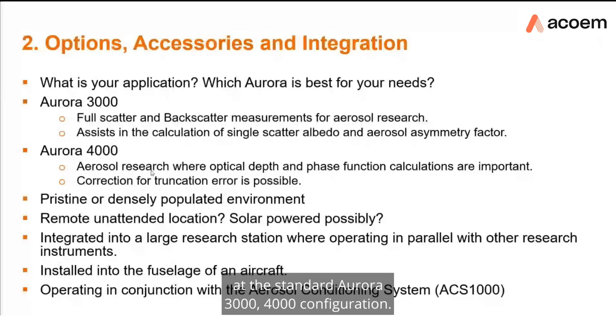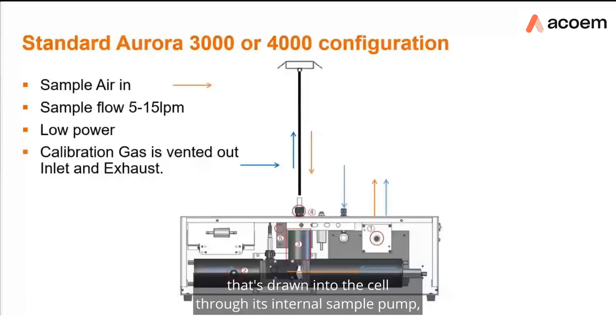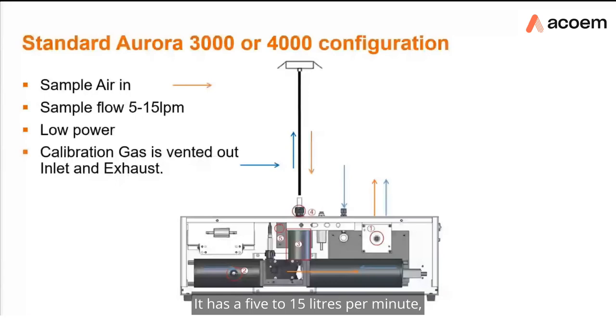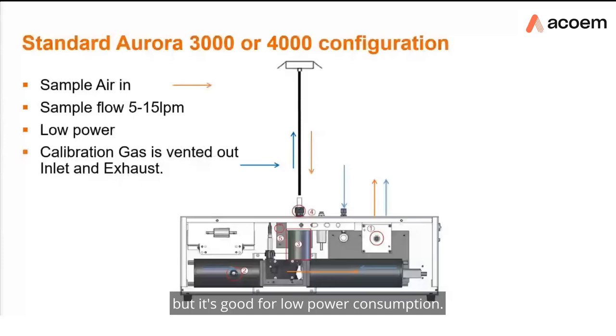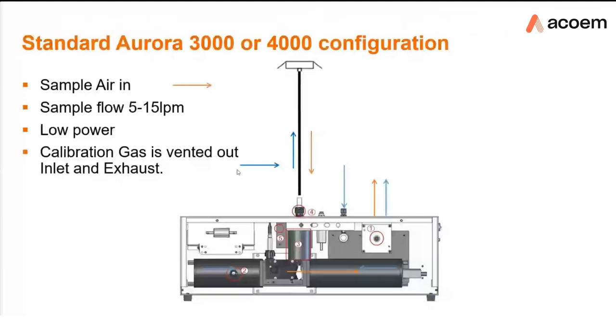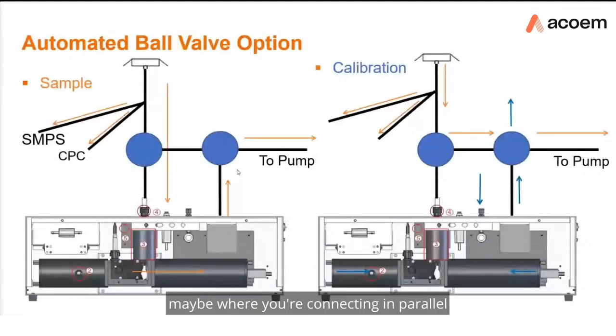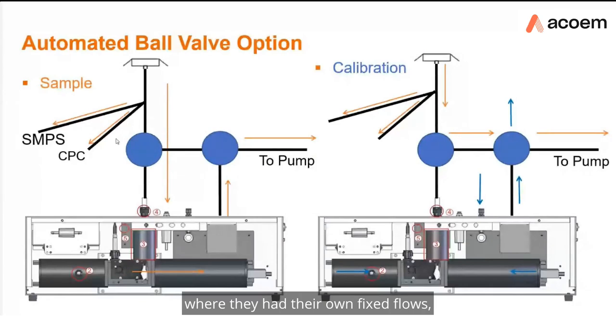The standard Aurora 3000 and 4000 configuration is a standalone setup where the sample inlet is drawn into the cell through an internal sample pump — a low-power blower motor running at 5 to 15 liters per minute. However, that flow is not regulated or controlled, so restrictions in the inlet can affect flow. Calibration gas is vented out both the inlet and the exhaust. This is the simplest configuration, good for use in parallel with other instruments that have their own fixed flows.